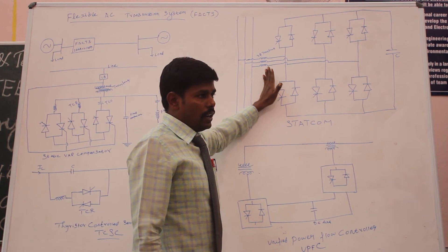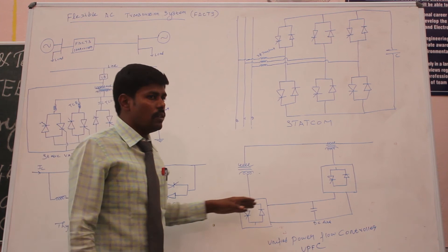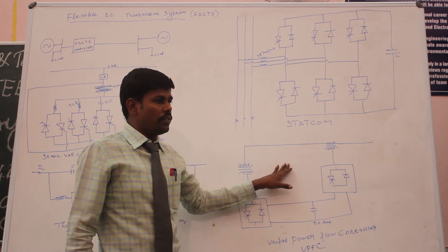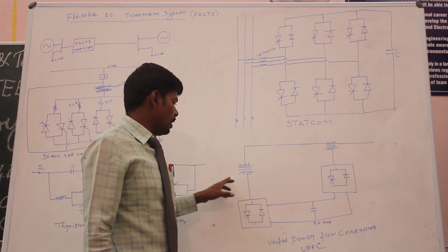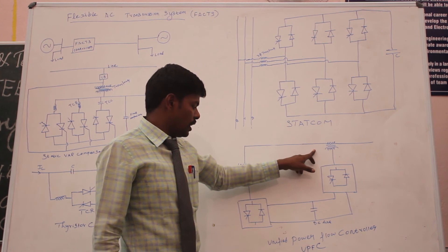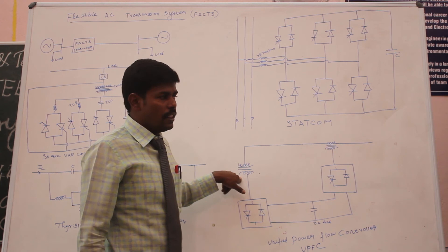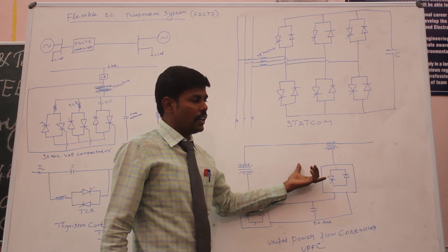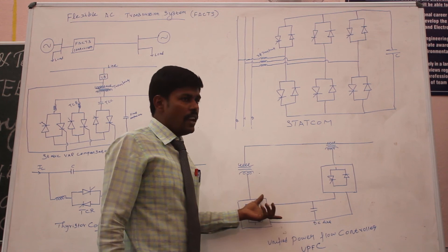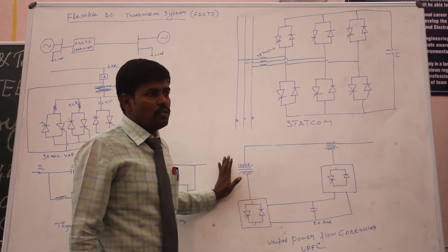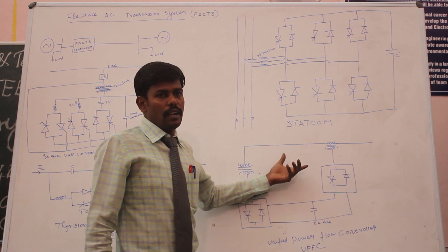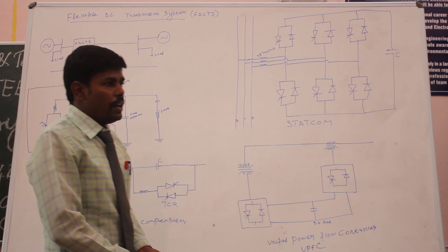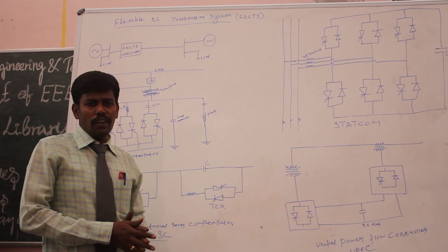Next is the unified power flow controller. This unified power flow controller is both a series and shunt controller connection. It is a bidirectional operation with a series and shunt controller. This transmission line connection has a series connection and a shunt connection — a shunt connected control rectifier and a series connected control rectifier. The transformers are connected in series and in shunt respectively. In between these two rectifiers we connect a DC link for the feedback system. Whenever there is a transient state in a power system, it automatically regulates the voltage and maintains the voltage at the receiving end. This is the unified power flow controller, and it is the main application in transmission and distribution, regulating voltage from the transient state to the normal steady state voltage.